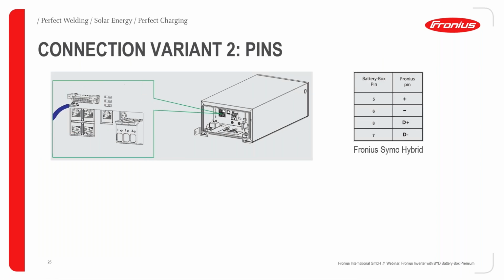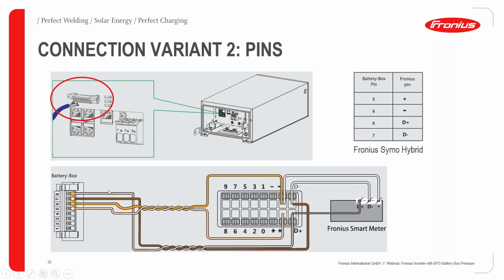The second variant is to use this terminal block, using bare cables rather than a plug on the end. This wiring diagram uses pins 5 through 8 with the corresponding pinouts. All this documentation is taken from the BYD, or Alpha Power, quick commissioning and configuration guide.